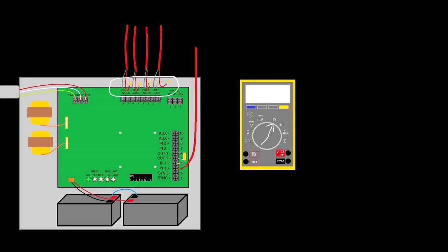Just to reiterate, before I had mentioned there's a couple ways to go about this first stage. One pretty good way would be to just disconnect these circuits one at a time and wait for that ground fault light to go out. That's fine, there's nothing wrong with that.